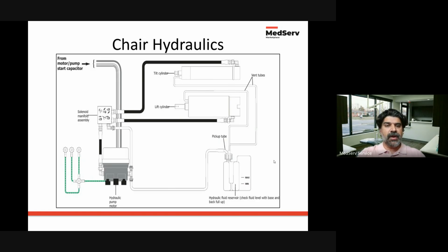This is a diagram outlining what the chair hydraulics look like. You can draw parallels to an electrical system as well. Instead of a cylinder, it would be an actuator. But the hydraulic pump or the reservoir supplies the pressure to the chair to drive the lifting, tilting, and movement of the different positions. Some common issues happen when you have a weak pump or a weak motor, to draw an electrical analogy. Sometimes the weakness can be associated with the pump or the motor not getting enough electrical power. Sometimes you'll notice the seat is not able to hold its position rigidly, and that is typically a wear and tear concept where the cylinder is not able to retain the pressure properly, or there are O-rings or some sort of valve that's not working properly.